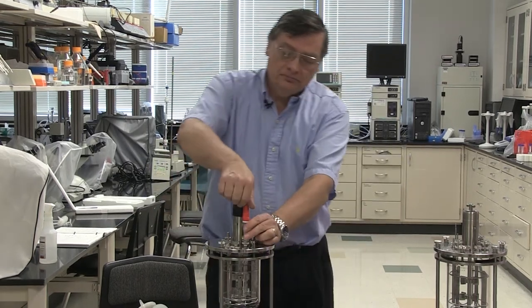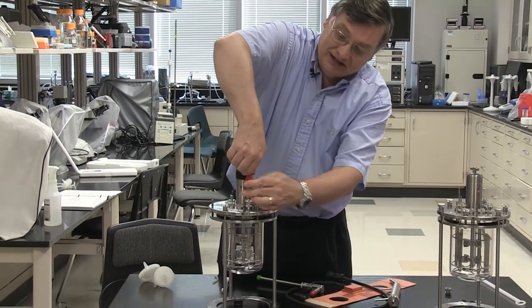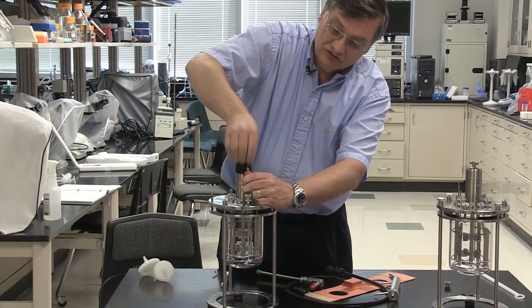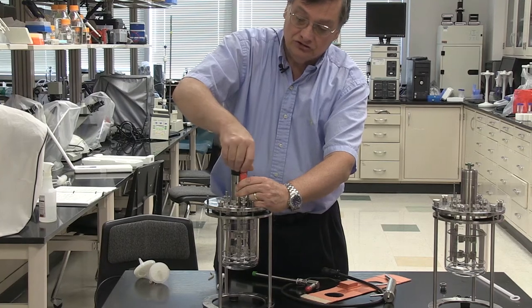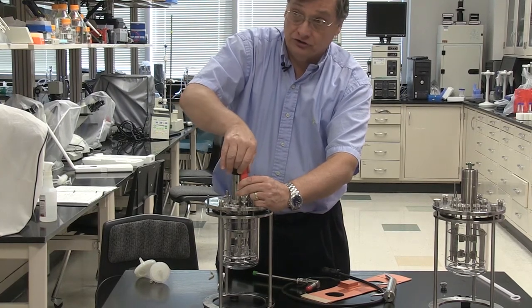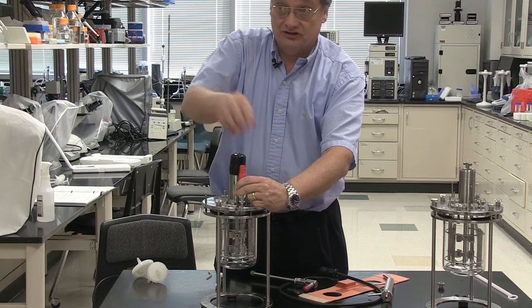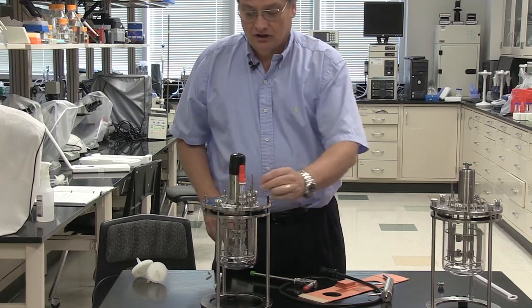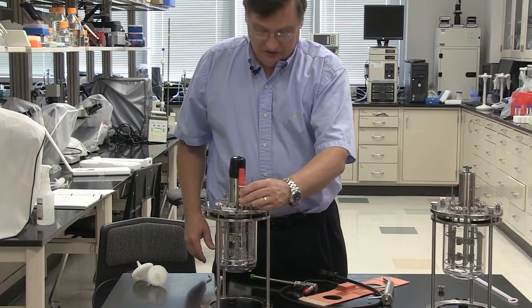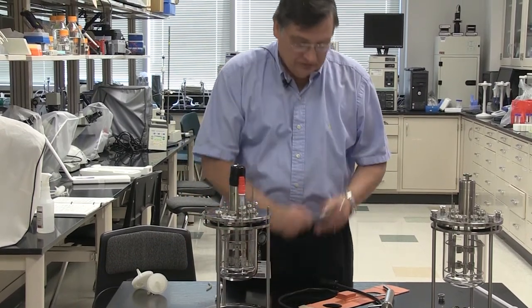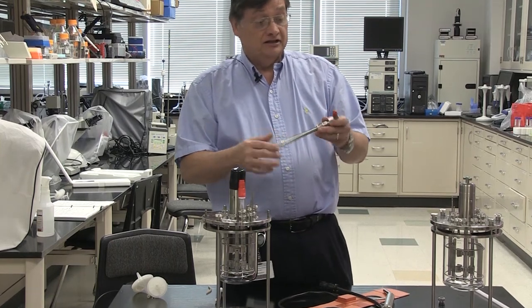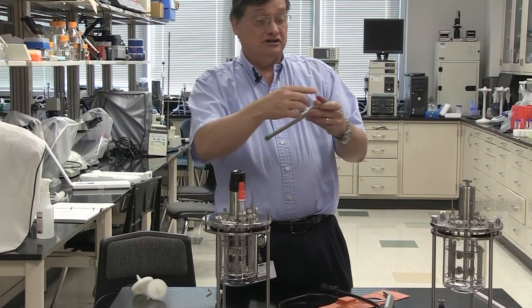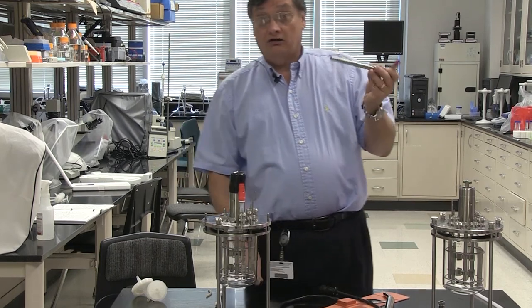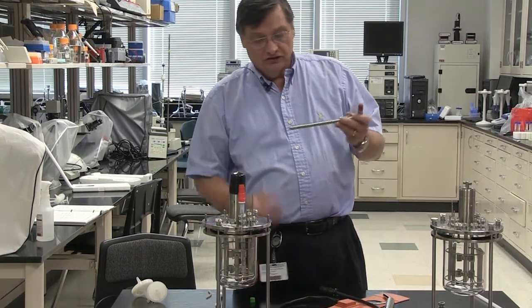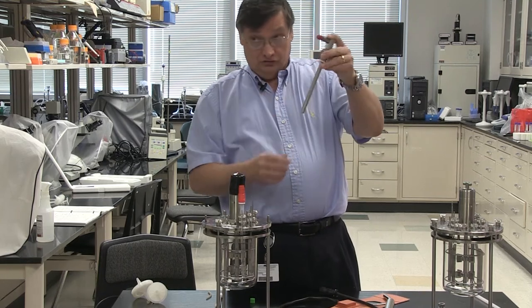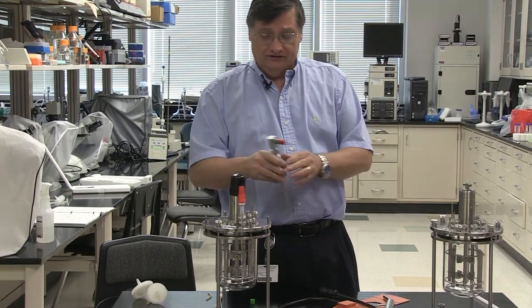You notice the pH probe here has this red cap on it. This is called a shorting cap. It's used during storage and also during autoclaving. But you'll remove this to attach the connector when you're actually operating the vessel. See, this is the DO probe, and it similarly has a cap at each end. This cap you'll take off. It's only used in storage, but this shorting cap is also used in autoclaving, so we're going to insert it in just a second.